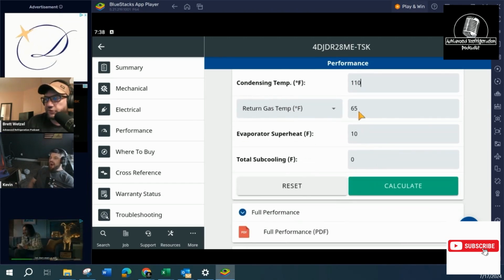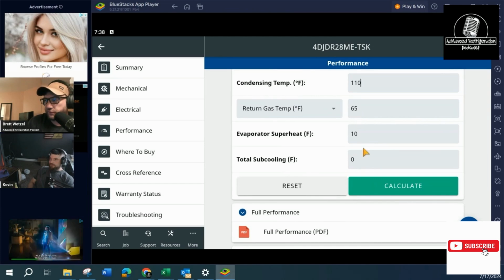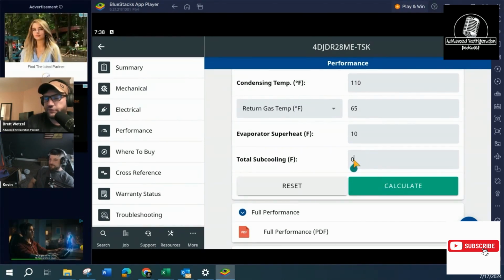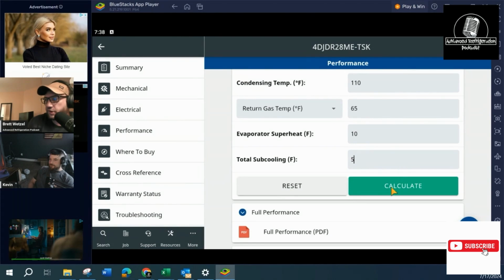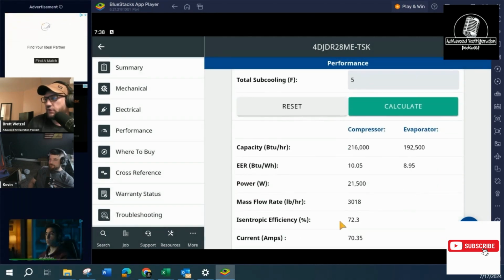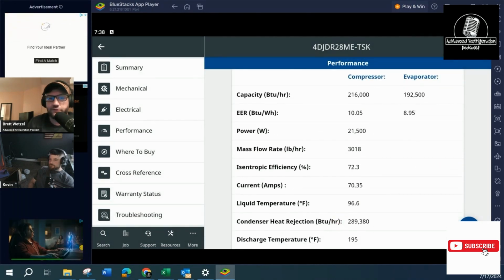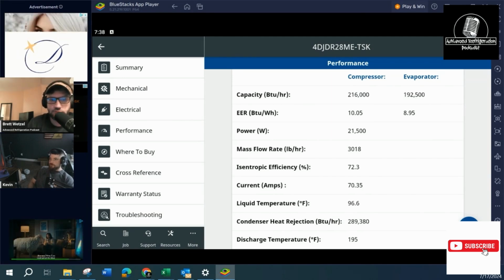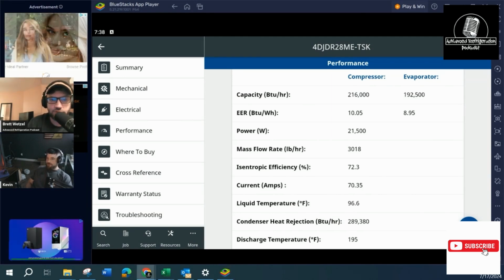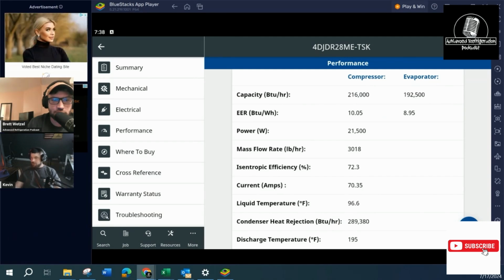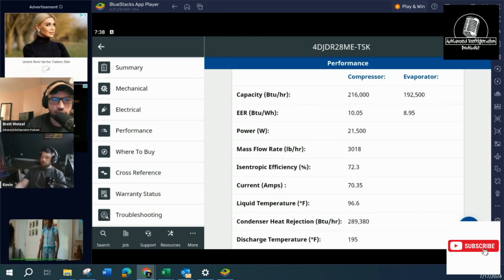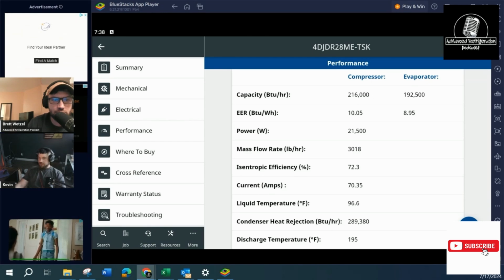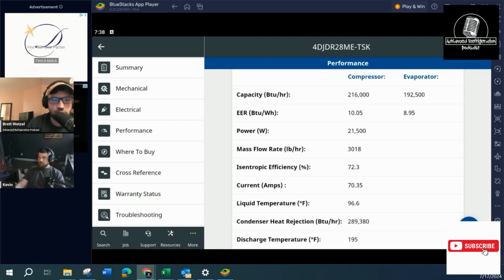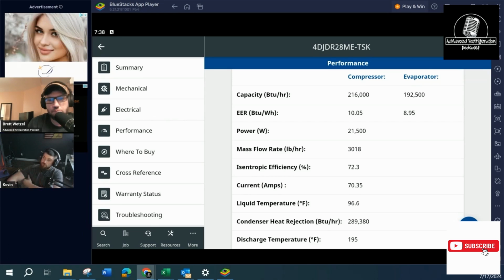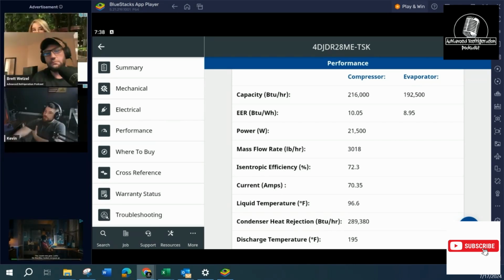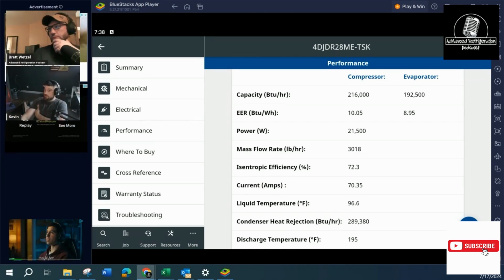Return temperature, do you want to go to a reasonable one? Leave it. Let's just run it. All right. And then just put like 5 degrees of subcooling, because that's usually what we get out of the condenser. So calculate. Given those two things, go ahead, you can explain it. Our current right now is at 70.35 amps. And our BTU capacity an hour is at 216,000 BTUs. It's a big compressor.